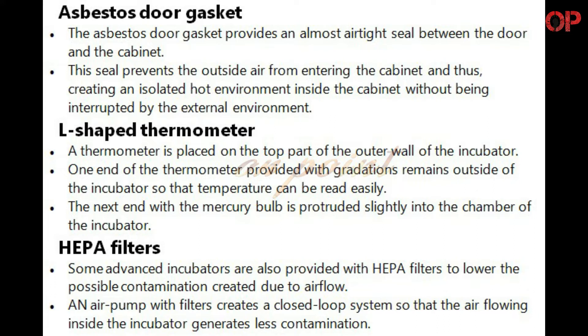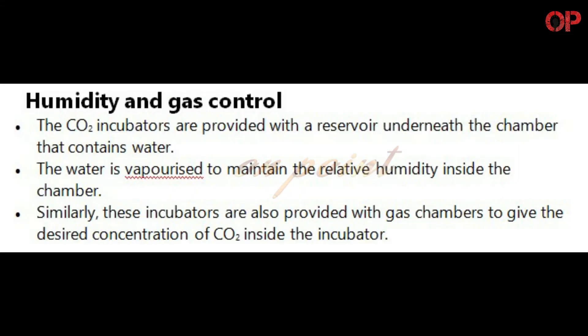HEPA Filters: Some advanced incubators are also provided with HEPA filters to lower possible contamination created due to airflow. An air pump with filters creates a closed-loop system so that the air flowing inside the incubator generates less contamination. Humidity and Gas Control: CO2 incubators are provided with a reservoir underneath the chamber that contains water. The water is vaporized to maintain the relative humidity inside the chamber. Similarly, these incubators are also provided with gas chambers to give the desired concentration of CO2 inside the incubator.